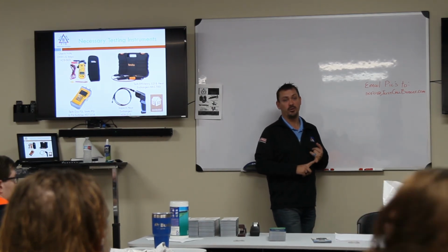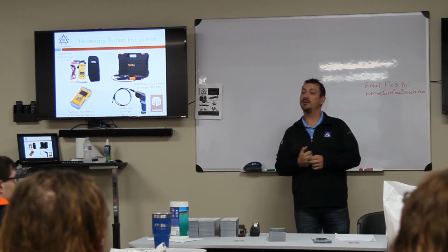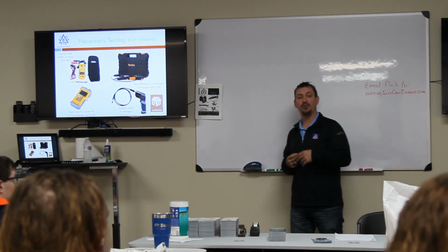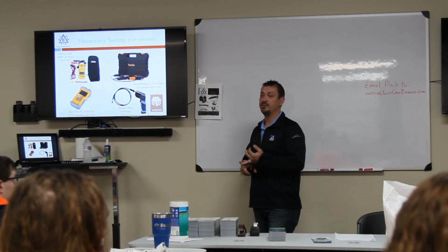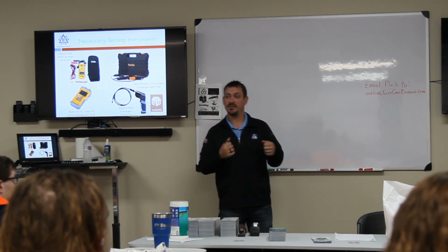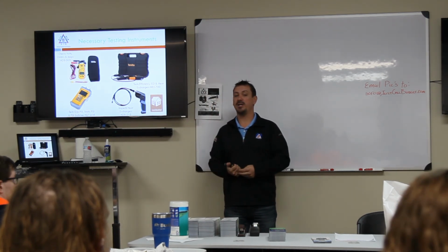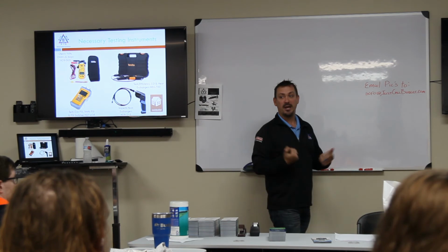And one of the things it's going to be able to do, that we talked about before, is check the efficiency of the equipment, so it can help to retain customers or gain new customers under these service contracts, where you can go there and say, your equipment was running at 68%. Once I left, I got it back up to 80%.